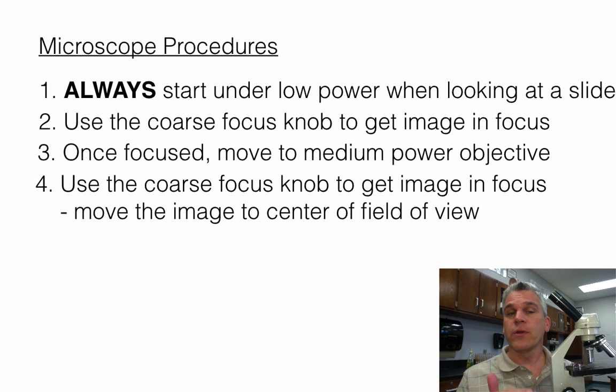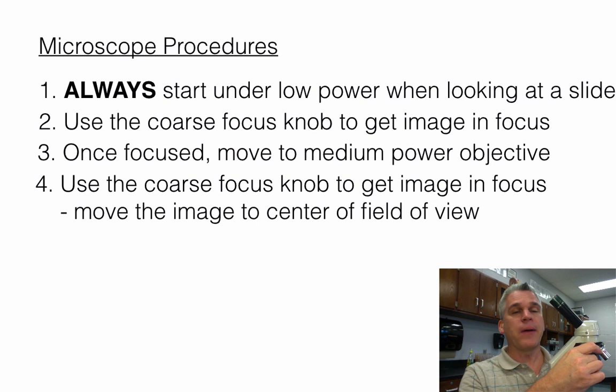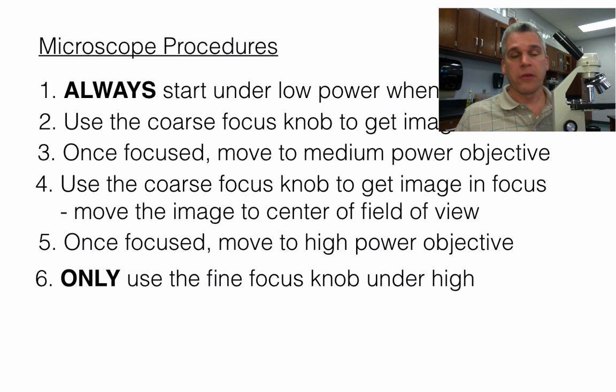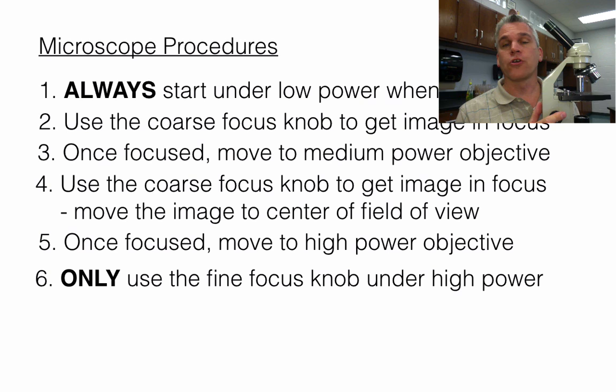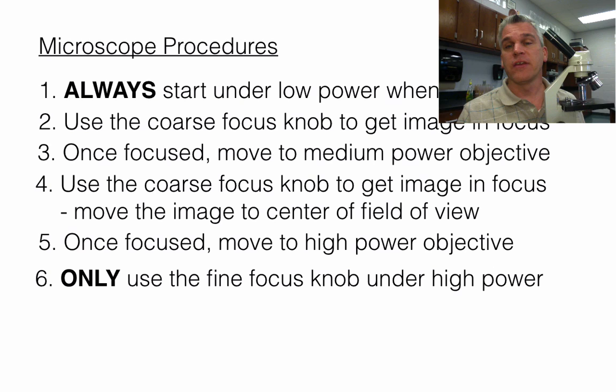Now if it's not in focus under high power, it will be very close. Use the fine focus knob under high power. Never use the coarse focus knob, because what can happen is the stage goes up into the objective and it can scratch the lens. Since the lenses are the most expensive parts, you will have just bought yourself a scratched lens.